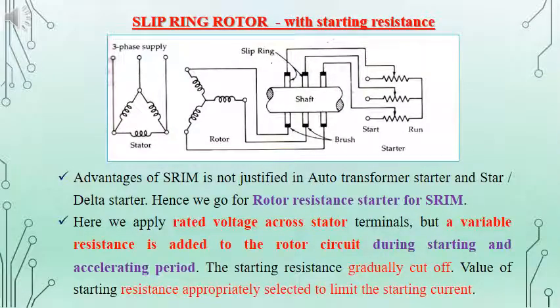Now we will consider the slip ring induction motor. For a slip ring induction motor, we have slip rings connected with the rotor circuit, and we can have a variable resistance system on the rotor circuit. Till now we were considering a lower voltage applied to the stator terminals for starting the induction machine, which reduces the starting torque too. Here, in the slip ring induction motor with starting resistances, we can apply the rated voltage itself at the starting condition, and for starting there will be resistances added to the rotor circuit. These resistances will be gradually cut off as the machine picks up speed, and they help to improve the starting torque and to reduce the starting current.